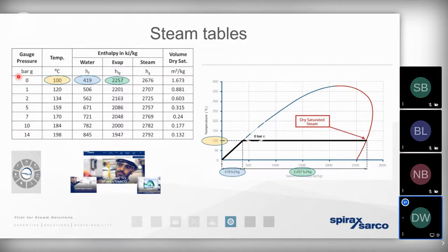It tells us the pressure-temperature and the pressure-volume relationship, but it also tells us that if we understand the pressure that the condensate exists at, we know both the temperature and how much energy is present within that condensate. And by observing the temperature-enthalpy curve, we appreciate that from time to time, depending upon how accurately and reliably we're operating the steam boiler, we are likely to get steam that is being produced in the wet steam zone. We won't be producing dry, saturated steam.